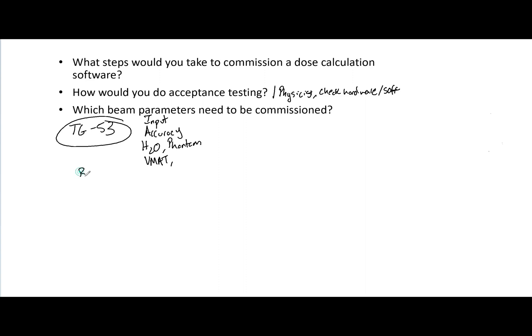Regarding which beam parameters need to be commissioned: first is the beam description — the energy, what you're going to call it, and what the default parameters are. You need to check the geometry, any type of beam modifiers such as trays, cutout factors, or any modifiers you might potentially have. You also want to define your field definitions, and you want to have information about your wedges and your normalizations. Be very familiar with beam configuration — what percent depth doses you've used and how you calculate your DLG.